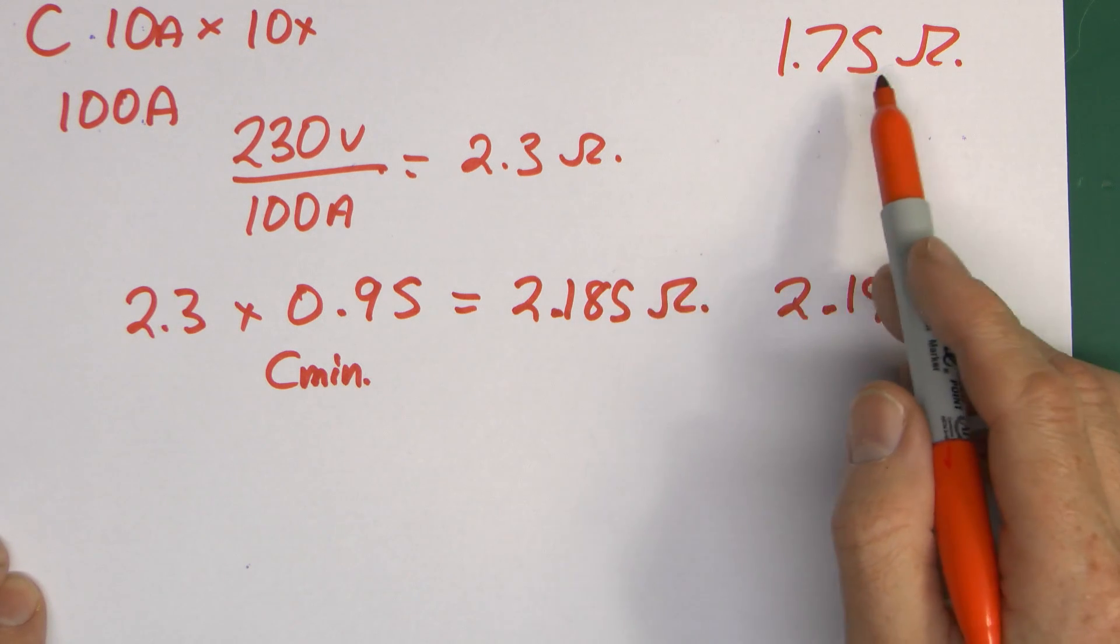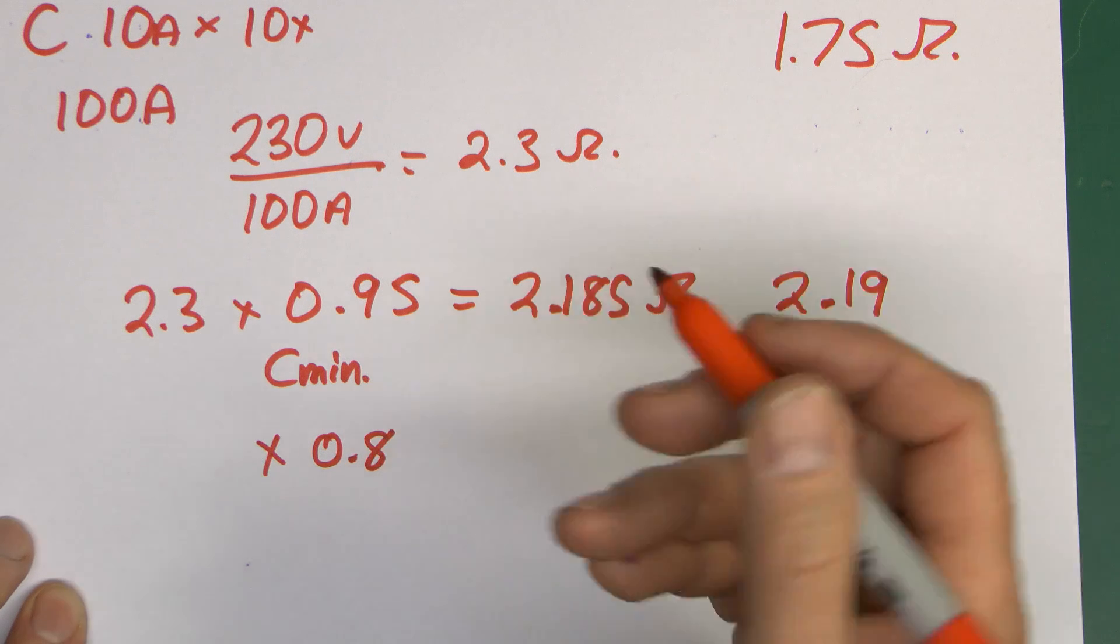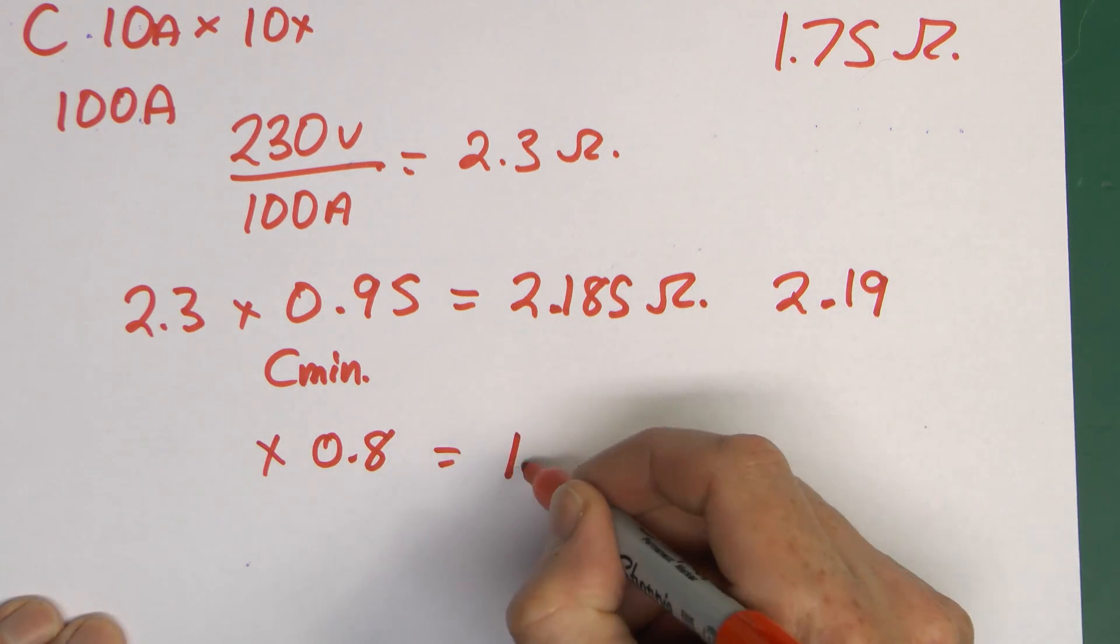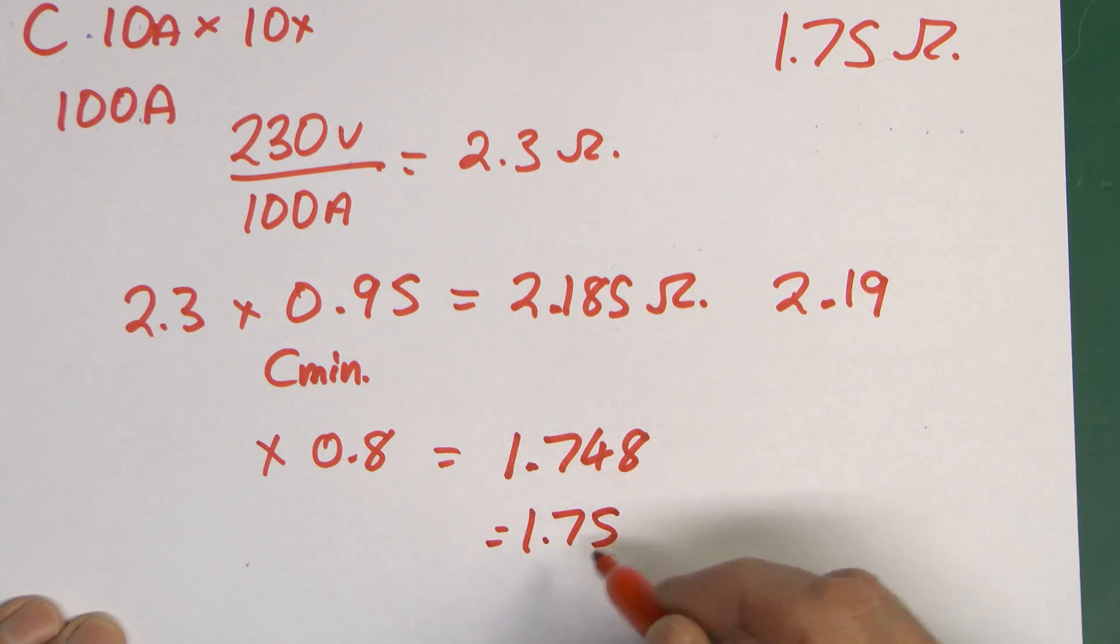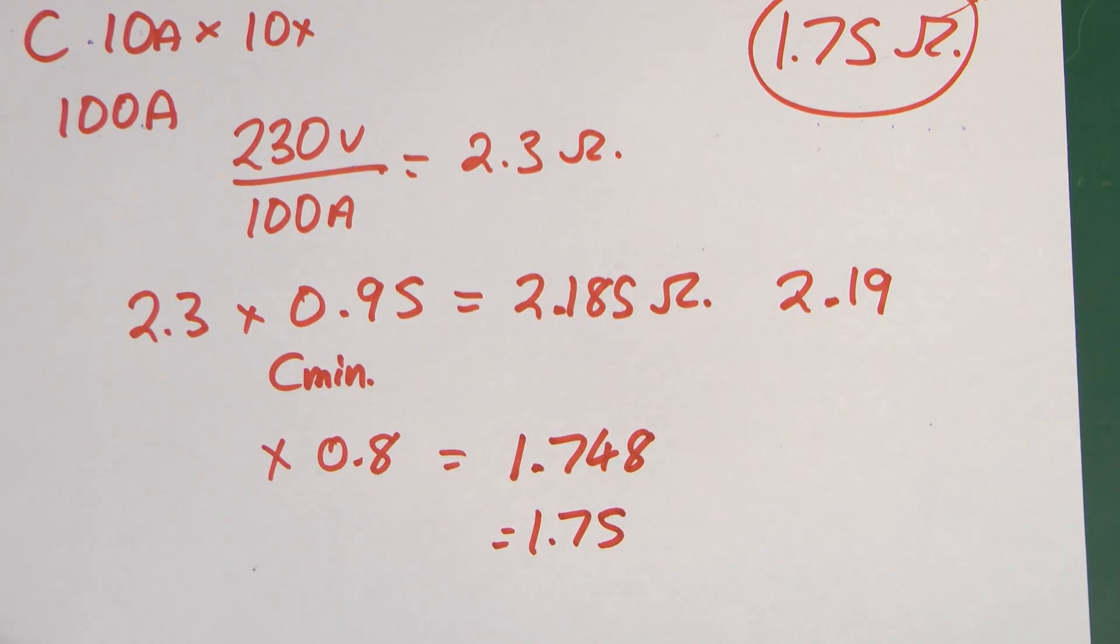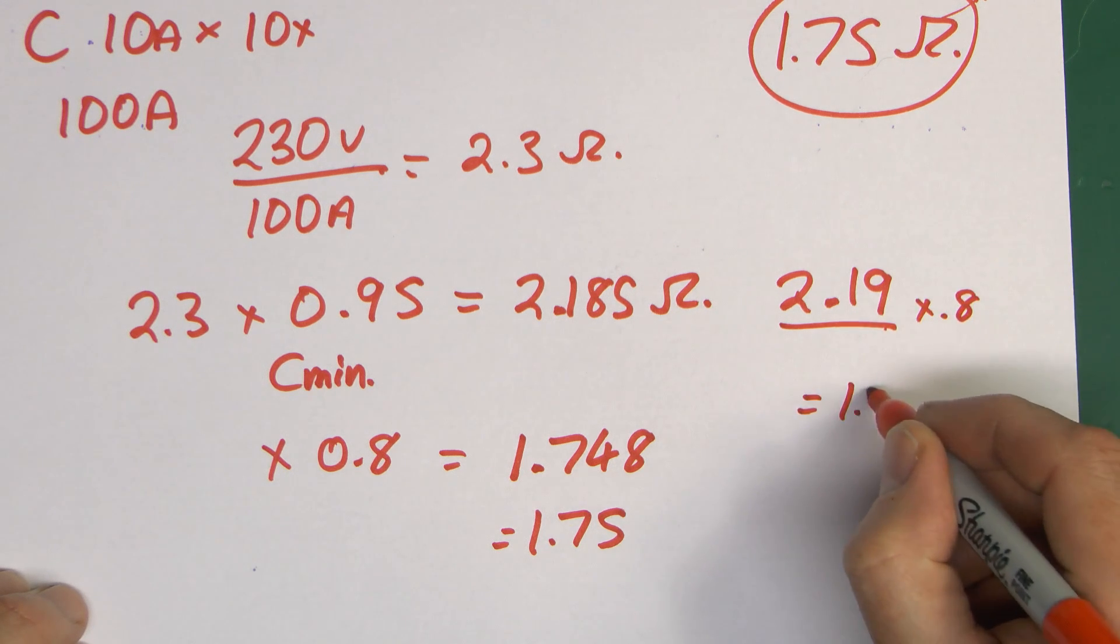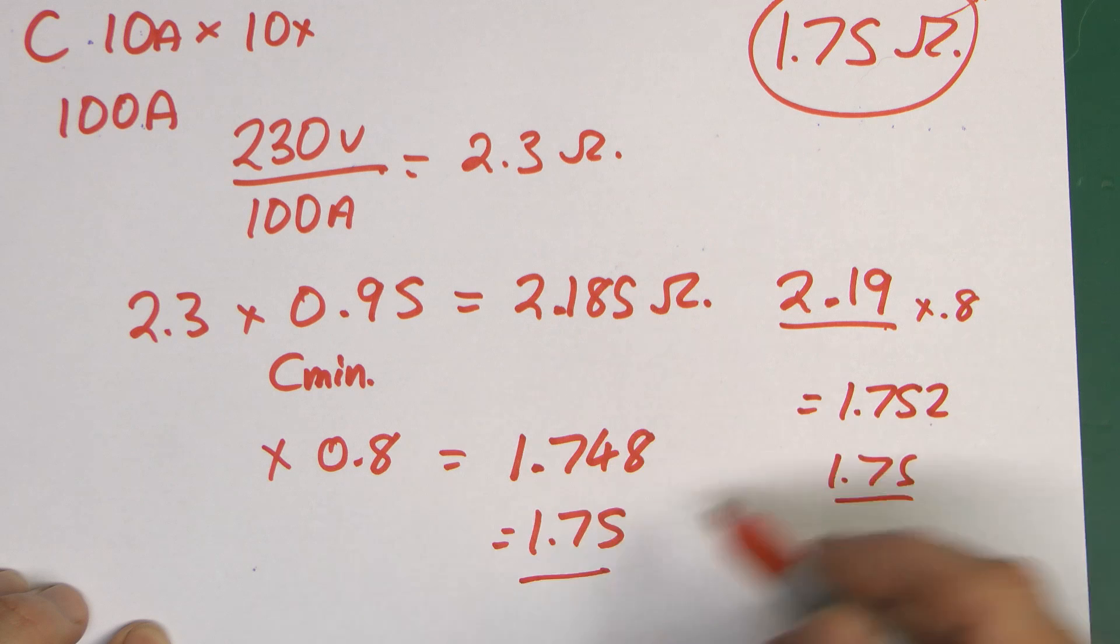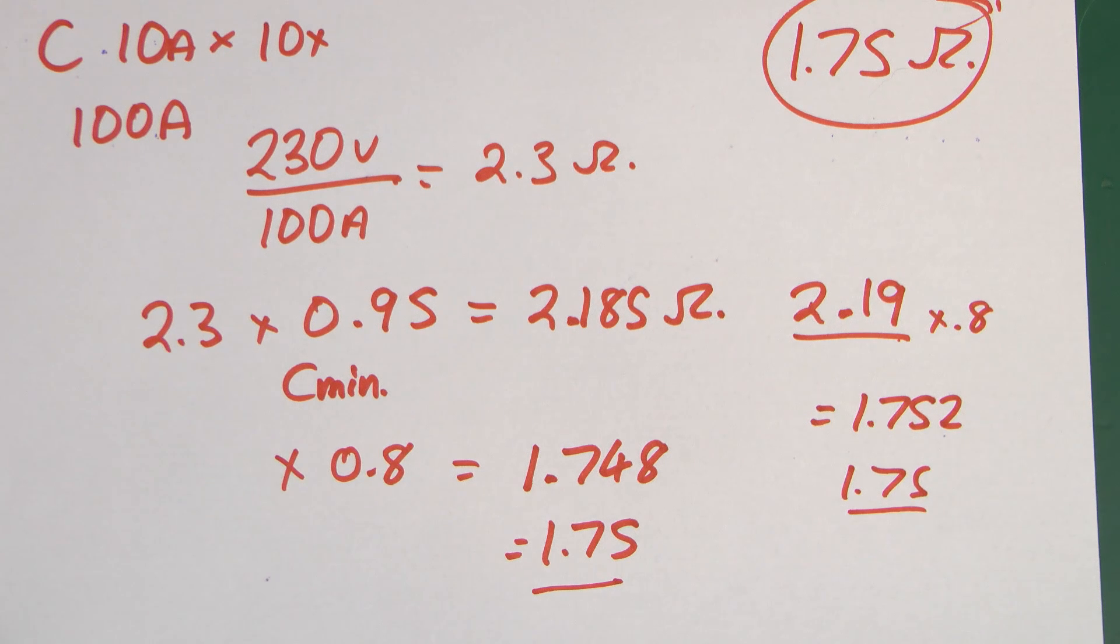And then to get the actual value we do normally use for an actual installation, again that's that 80% value, so multiplying by 0.8 or 80% basically. And if we use the full value here, the 2.185, then the value we get is 1.748. And again, we're going to just round that off to the two decimal places. 8 is obviously a fairly high number there, so we end up with 1.75, which again is what's printed on the sheet there. If you actually use the rounded off value of the 2.19 and multiply that by 0.8, then you actually get 1.752, which again is still 1.75. So in that particular case, you actually get the same value regardless of where you round it off. As I said before, it doesn't really matter. 0.01 ohms is not really going to change anything in any practical terms.